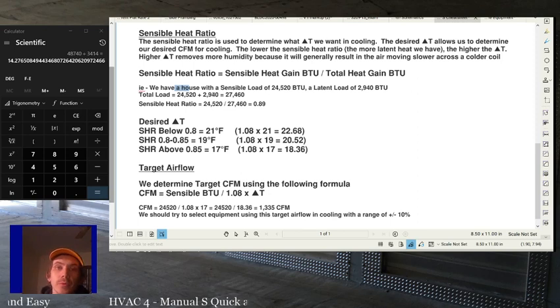So in other words, there's a pretty high heat gain for the size of the house, but not much of it is latent, mainly because most of our latent load comes from infiltration. Okay, most of our latent load comes from infiltration from outside air to the inside, and that brings in the humidity from the outside, which adds to our latent load. People don't add that much latent load. It's like 200 BTUs per person or something. So most of that comes from the outside because there's nothing else that adds latent load except for people and outside air. If you go back to your load calcs, you'll see that.